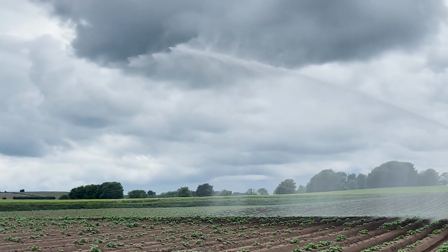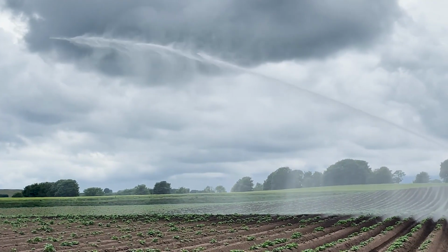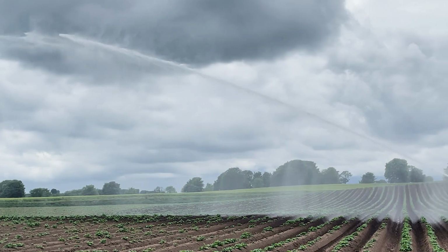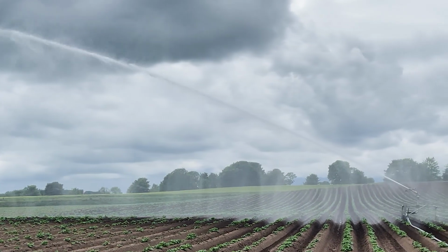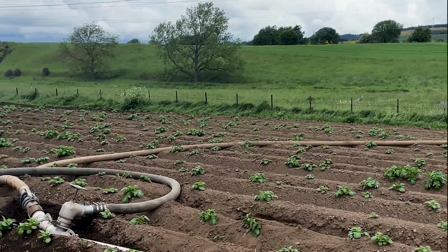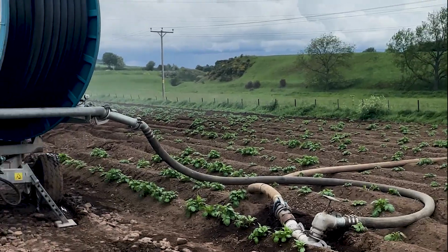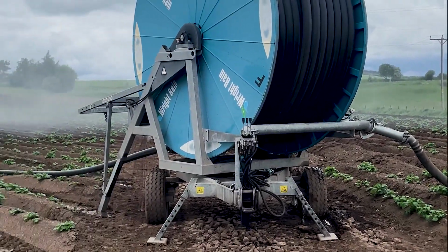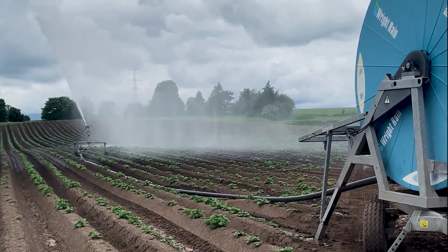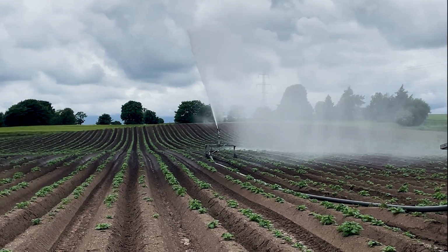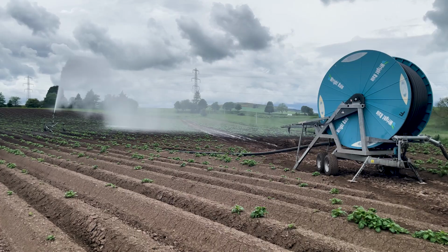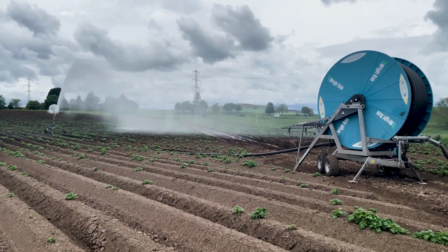So next steps: measure what matters. Meters on main lines pay for themselves by finding leaks and confirming peaks. Match peaks with buffering. Storage and correct pump or pipe sizing turns a fragile system into a robust one. Reality check the paperwork as well. Ensure licence limits and conditions align with your calculated peak needs before the season starts.